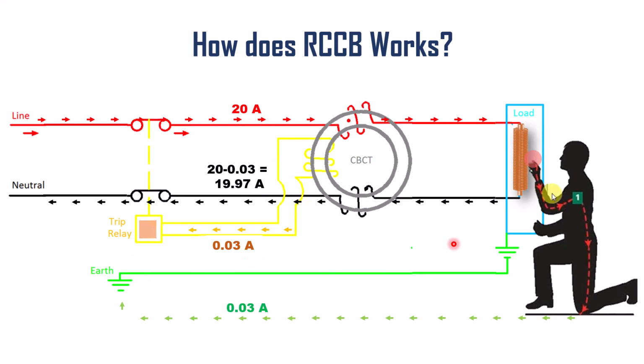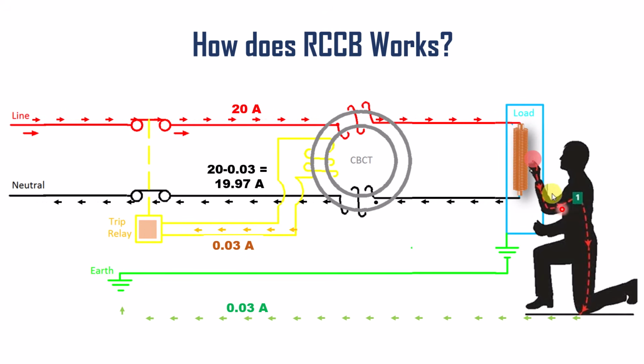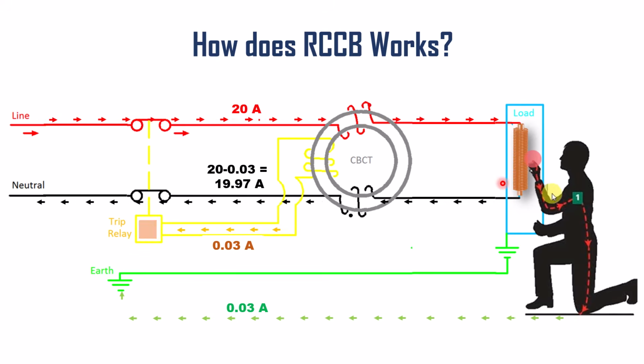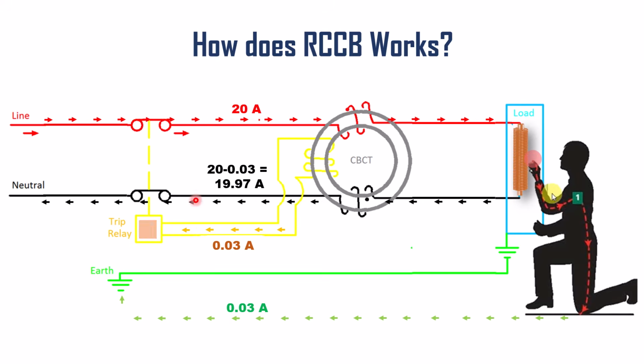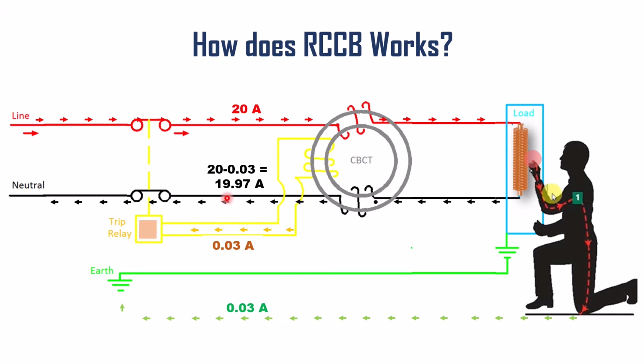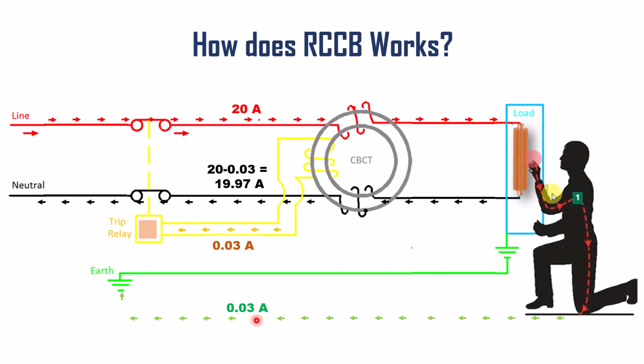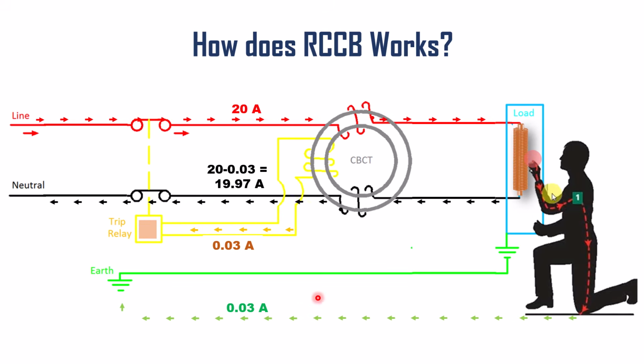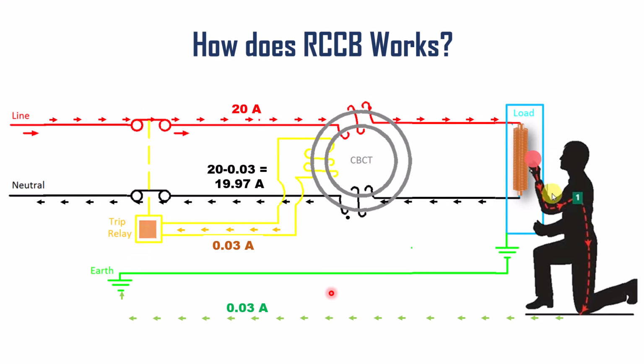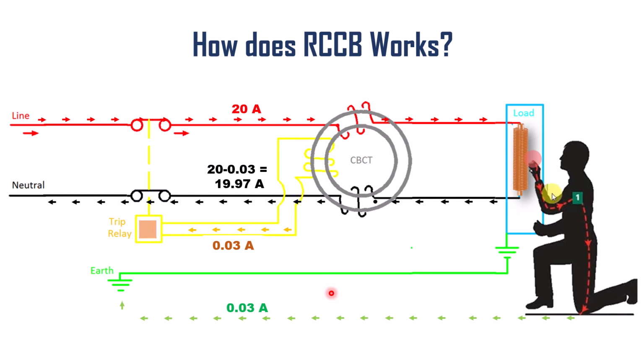Now again let's analyze the situation when the human comes in contact with the phase conductor. If only an MCB is installed, it can only protect against overload or short circuit current, but it does not trip on this small leakage current, which is almost 30 milliamperes. That's where RCCB comes in. It can detect leakage current as small as 30 milliampere and trip instantly, making it a life-saving device. So in conclusion, we can say that MCB protects equipment while RCCB protects human life. That's why both must be installed together in an electric circuit.